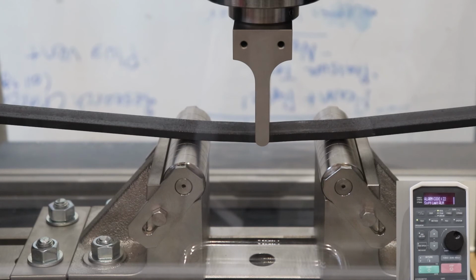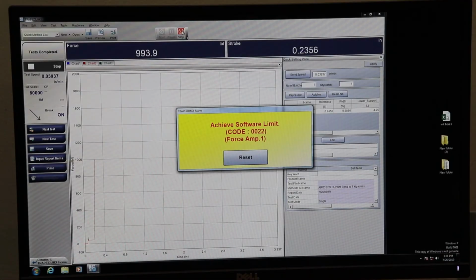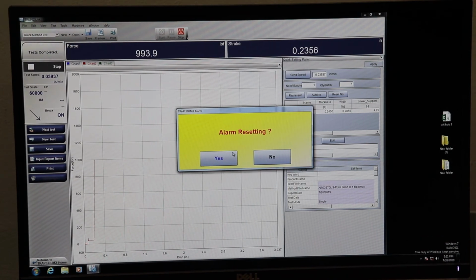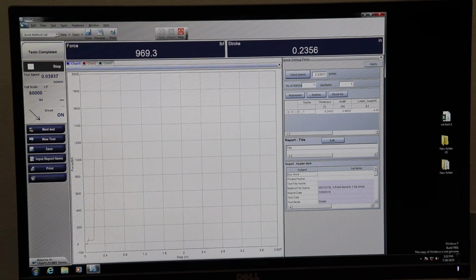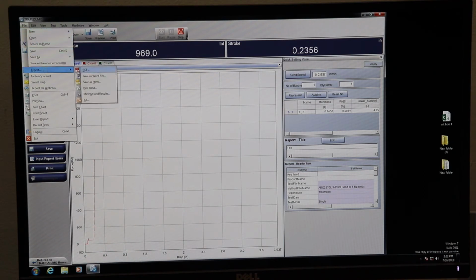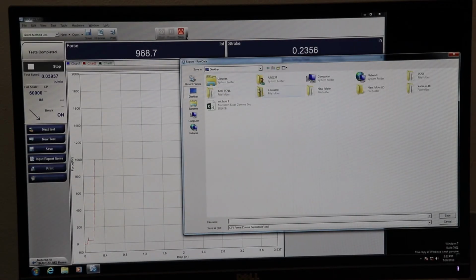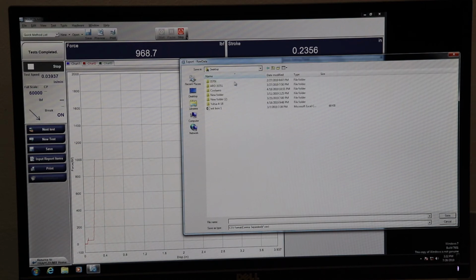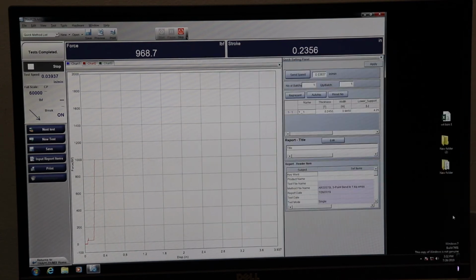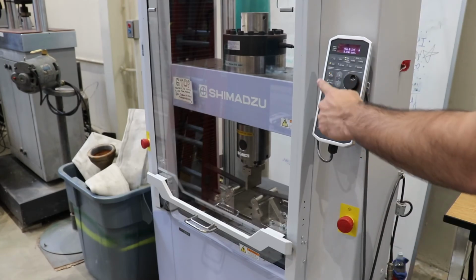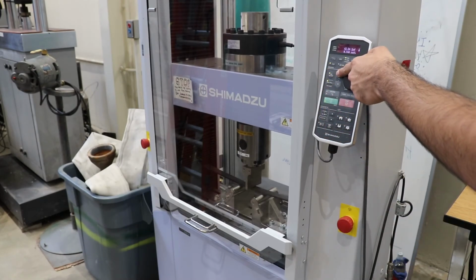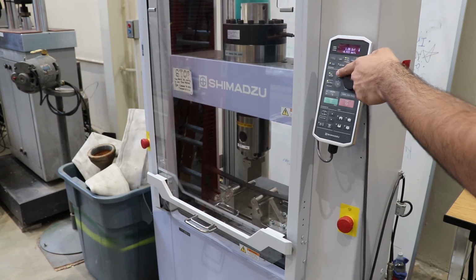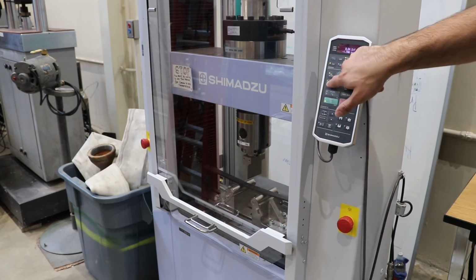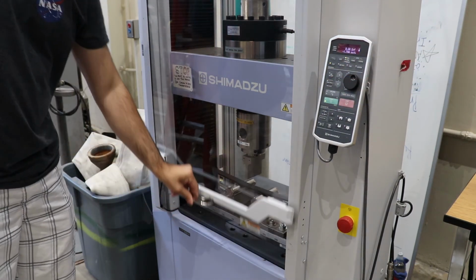Once the machine reaches its maximum load, an alarm will sound. We will reset the alarm in the software. At this point, we will save our data to the desktop and then to a USB drive. We will now unload the specimen by jogging the head up. After doing so, the specimen is able to be removed.